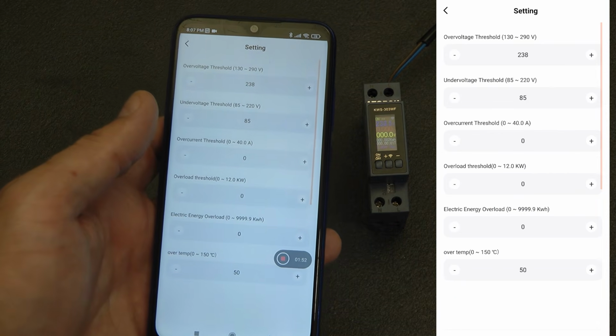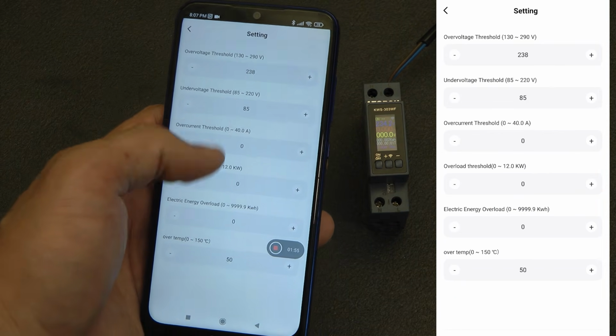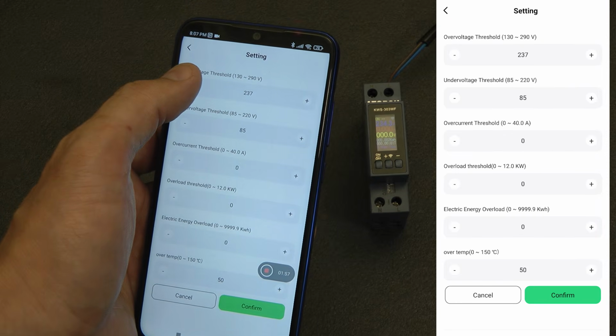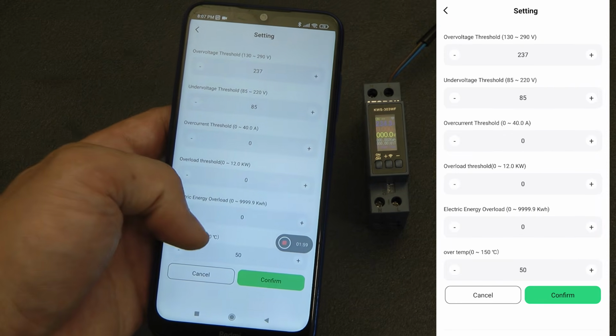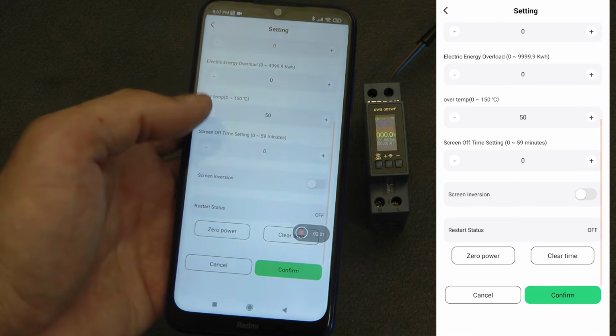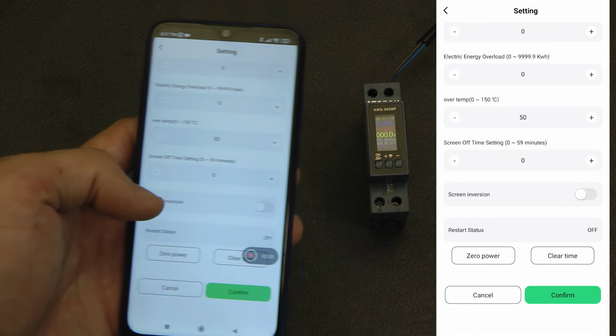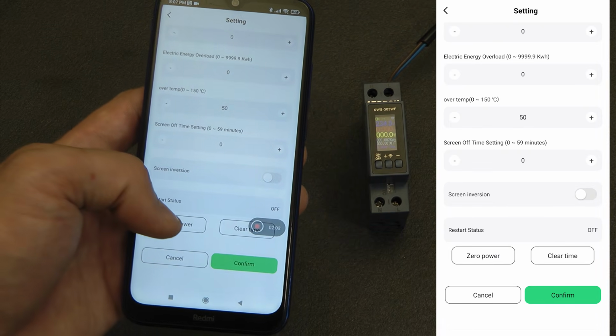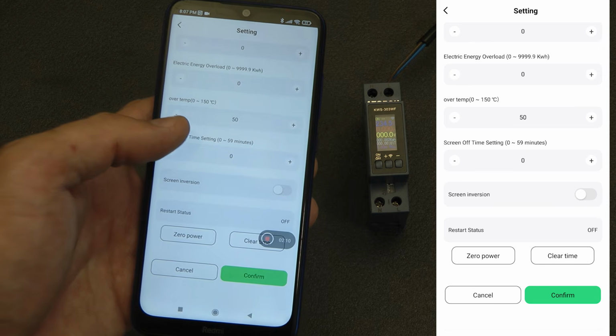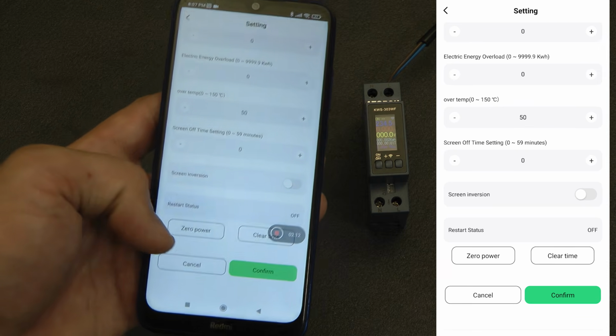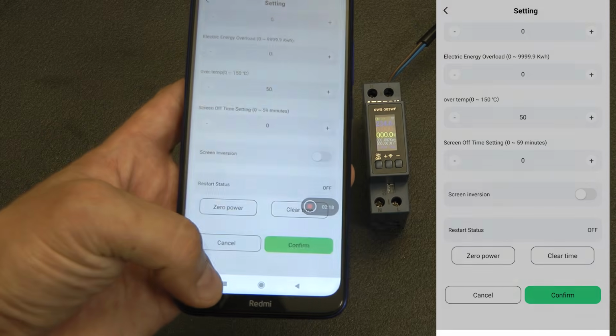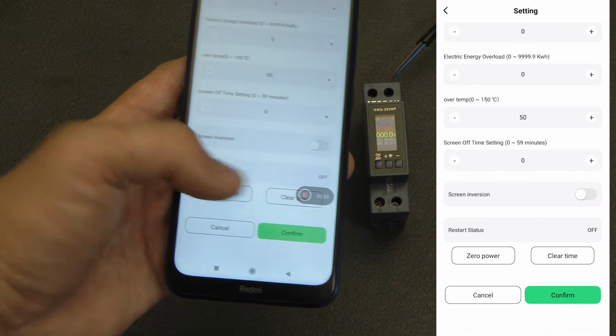The settings in the app almost completely repeat the menu of the relay itself. Here you can set the upper and lower voltage thresholds, limits for current, power, consumed kilowatt-hours, and temperature from the external sensor. Below that, you can configure the display timeout, screen rotation, and relay state after a power loss: off, on, default, or memory of the last state. There are also buttons to reset kilowatt-hour statistics and operating time.